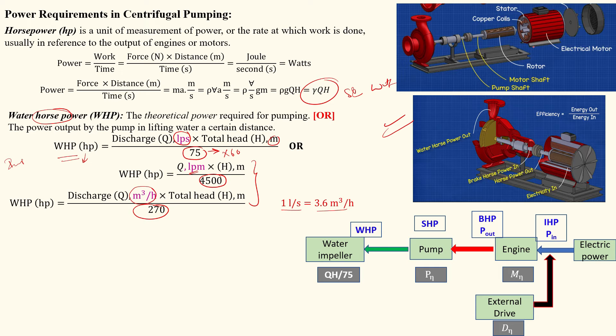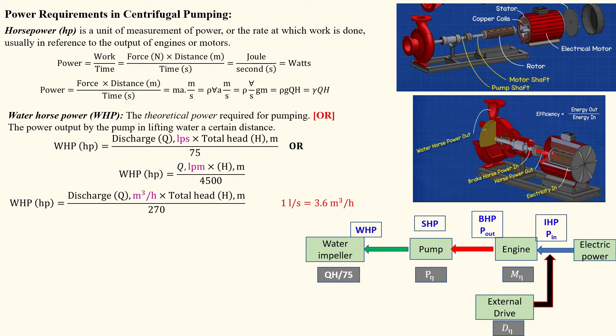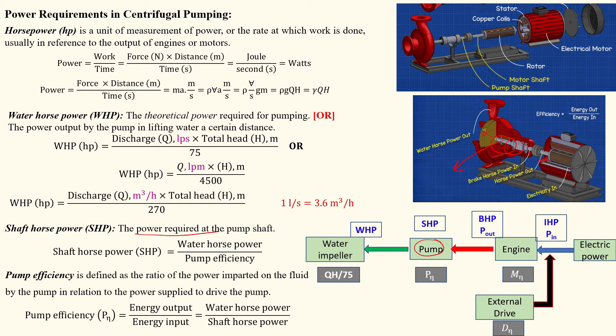Now consider the energy flow diagram. Electric energy comes into the motor, which rotates and is attached to a shaft. The shaft connects to the impeller. The total energy output available at the impeller is called water horsepower. The shaft horsepower is defined as the power required at the pump shaft. It is calculated as water horsepower divided by pump efficiency.